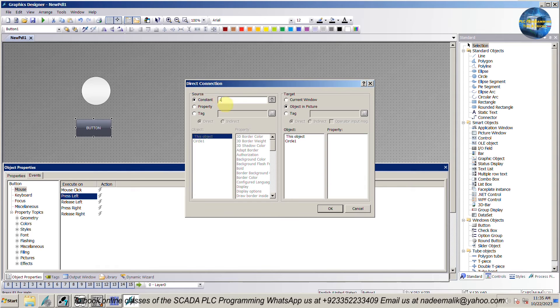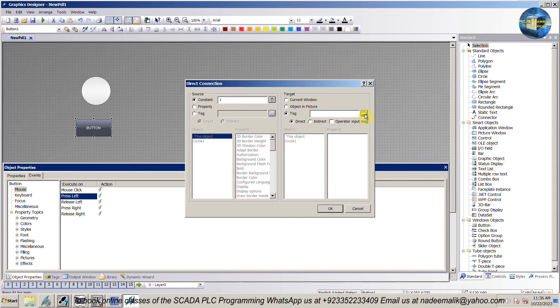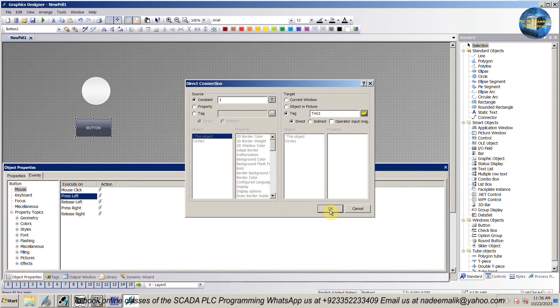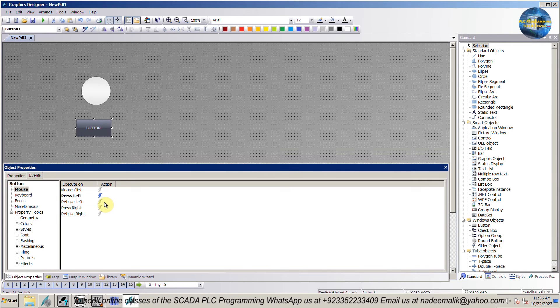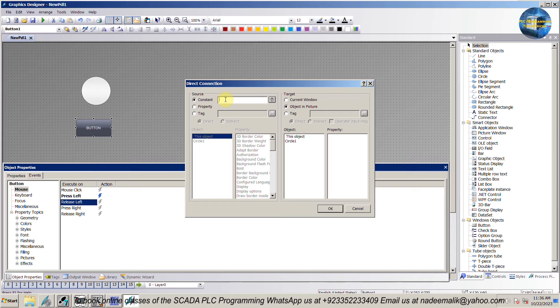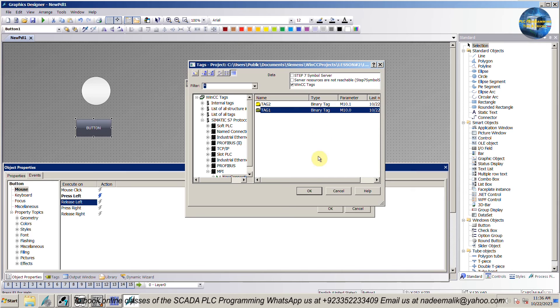In the constant we will put value 1 — when we click on this button, this will set the tag value to 1. Next in the tag menu, we will select tag 1 which we created earlier in the tag management menu. Next select the release left option, right-click and select the direct connection option. In the constant we will put value 0 — when we release the button, this will set the tag value to 0. Next in the tag menu, we will select tag 1 which we created earlier in the tag management menu.